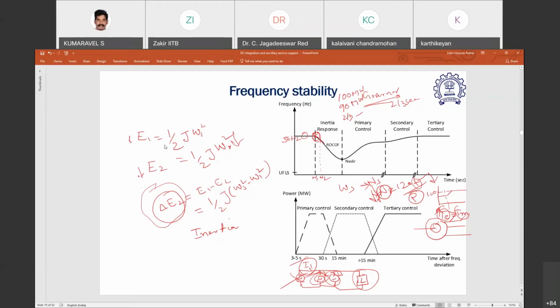And it is this inertia, then later on the governor starts kicking in, and then it starts increasing the power depending on the ramp rate of the generator, and then the speed of the machine comes back. Okay, so once this governor kicks in, after 2-3 seconds, the frequency is brought back to the new steady state value by this primary frequency control. But it is not necessarily going to be the value of the frequency before the disturbance.